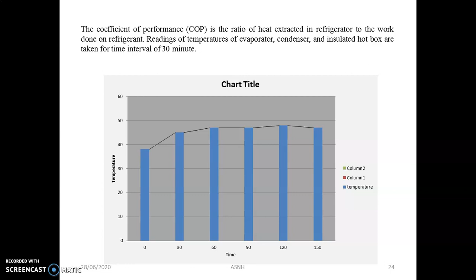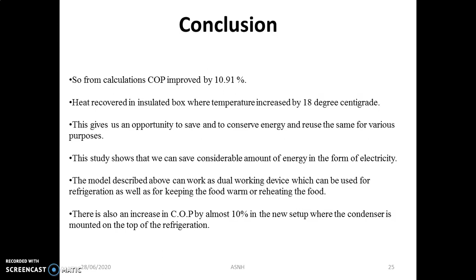In a similar way we can implement this kind of concept for water heating applications. Sometimes we need warm water for the kitchen also. So the conclusion is, from calculation the COP is improved by around 11%. In the heat recovery insulated box, the temperature is increased by 18 degrees as compared with the normal setup. Generally the temperature was near about 30, but after implementing this we get a temperature around 48 degrees Celsius. So this is a big achievement. There is also an increase in the COP by almost 10% in the new setup where the condenser is mounted on the top of the refrigerator.